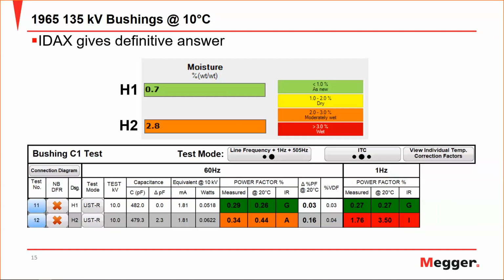So that way you can further plan and say, okay, we need to replace this bushing, but we can do it within 6 months or a year. But again, you may not have the IDAX. It may just be a small planned outage for a day. You may not have the time to do this additional testing. But if you have the 1 Hertz, you can then have the power to know and better plan for what your next testing or next actions would be for that particular asset.